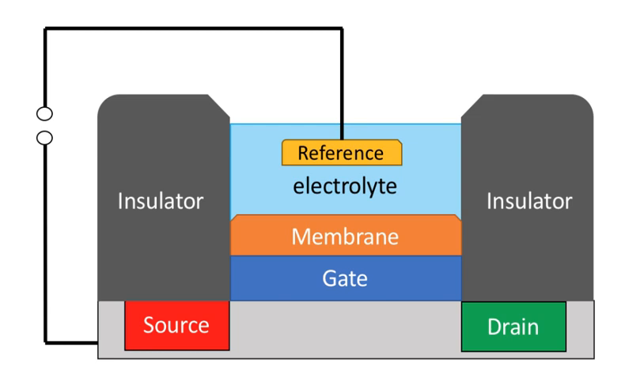Here, the analyte solution separates the source and gate electrodes. A concentration gradient between the solution and the gate electrode arises due to a semi-permeable membrane on the FET surface containing receptor moieties that preferentially bind the target analyte. This concentration gradient of charged analyte ions creates a chemical potential between the source and gate, which is in turn measured by the FET.